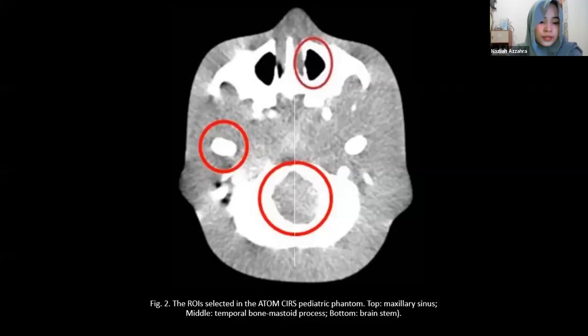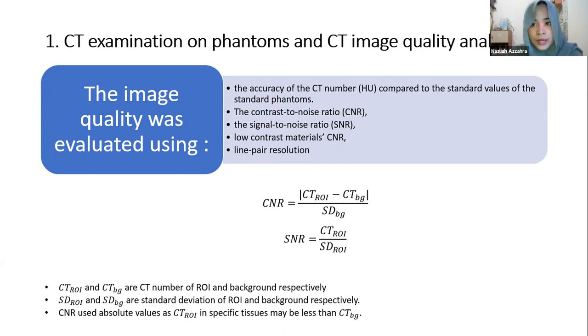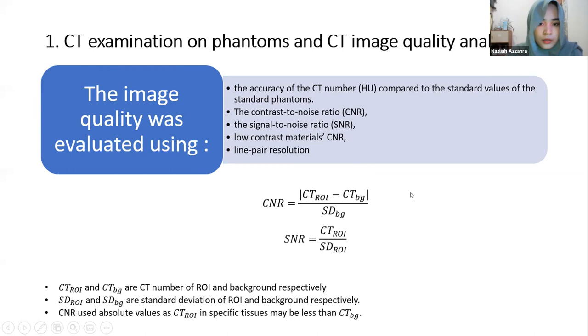There are three analyses in this study. The first is CT examination on phantoms and CT image quality analysis. Two phantoms are used, and image quality was evaluated using five parameters: the accuracy of CT number (HU) compared to the standard phantom value; contrast-to-noise ratio (CNR); signal-to-noise ratio (SNR); low contrast material CNR; and line pair resolution. CNR and SNR can be calculated using the equations shown on screen.